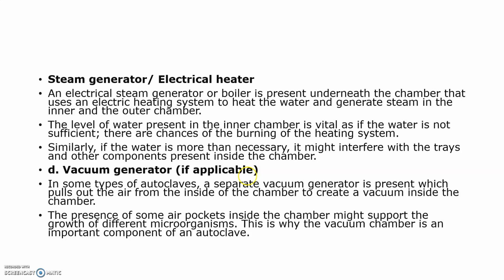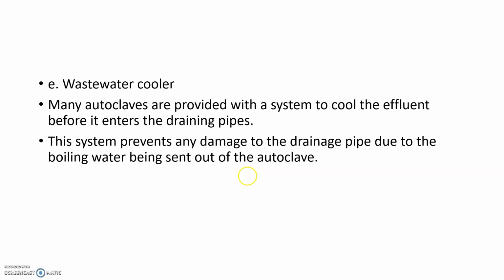Next is the vacuum generator. It is not present in all, but if applicable, in some types of autoclaves a separate vacuum generator is present, which pulls the air out of the chamber to create a vacuum inside the chamber. Because air pockets inside the chamber might support the growth of different microorganisms. That's why the vacuum generator is important. Next is the wastewater cooler.